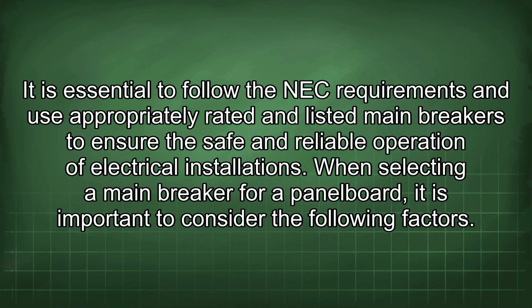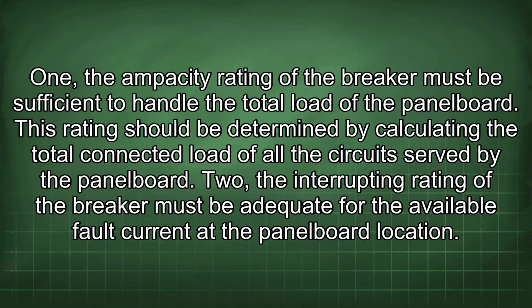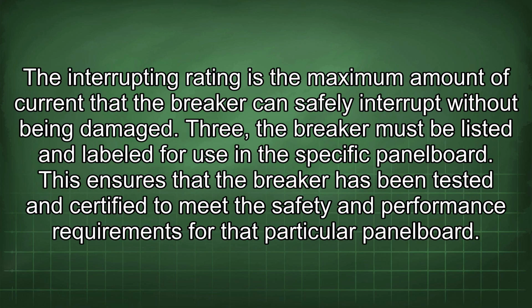When selecting a main breaker for a panel board, it is important to consider the following factors. 1. The ampacity rating of the breaker must be sufficient to handle the total load of the panel board. This rating should be determined by calculating the total connected load of all the circuits served by the panel board. 2. The interrupting rating of the breaker must be adequate for the available fault current at the panel board location. The interrupting rating is the maximum amount of current that the breaker can safely interrupt without being damaged.